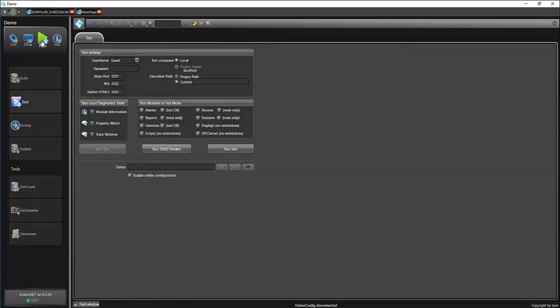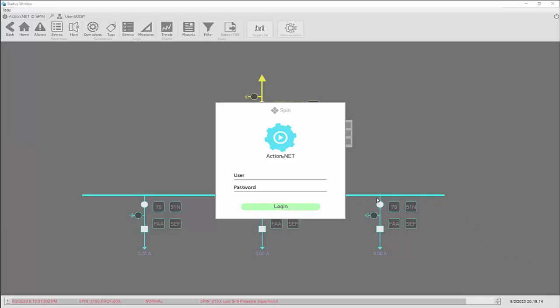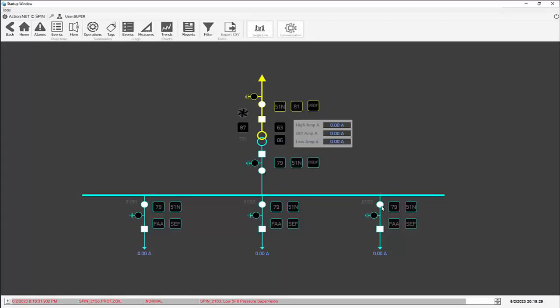The demo application is ready, the new 21S3 feeder has been added, and let's run it to see if everything is okay. In our simulator, there are already 3 simulated feeders. Go to Run, Start Up, and activate Demo. The demo automatically connects to the simulator. And if we command the circuit breaker, it opens, de-energizing the feeder, as shown.